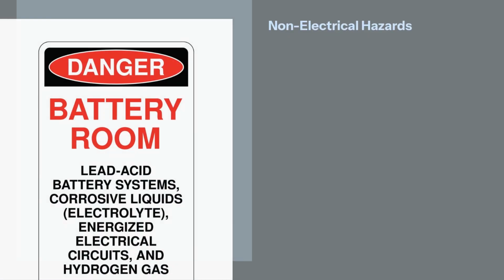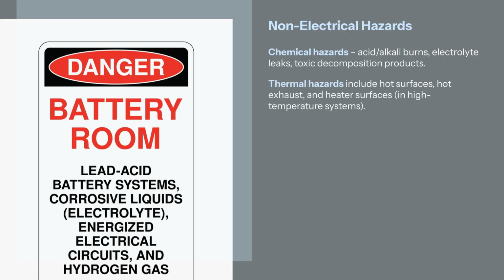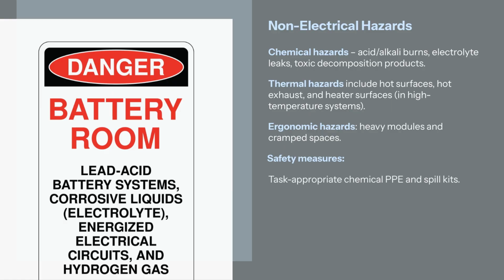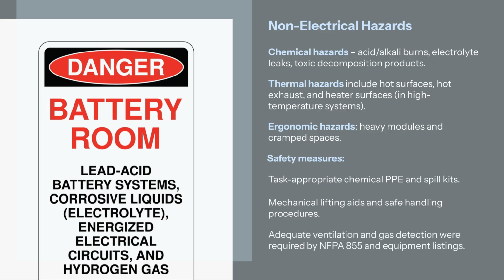When dealing with batteries, we must also remember non-electrical hazards. Even when electrically safe, batteries introduce chemical hazards: acid and alkali burns, electrolyte leaks, toxic decomposition products. Thermal hazards include hot surfaces, hot exhaust, and heater surfaces in high-temperature systems. Ergonomic hazards: heavy modules and cramped spaces. Safety measures include task-appropriate chemical PPE and spill kits, mechanical lifting aids, and safe handling procedures. Adequate ventilation and gas detection are required by NFPA 855 and equipment listings.